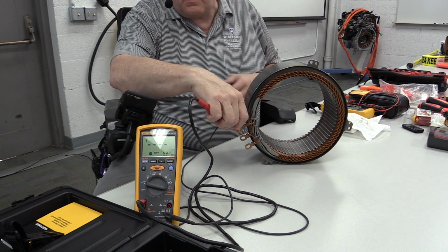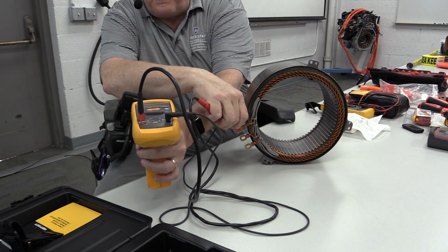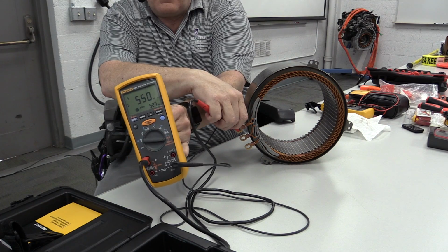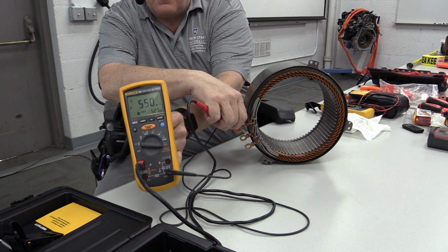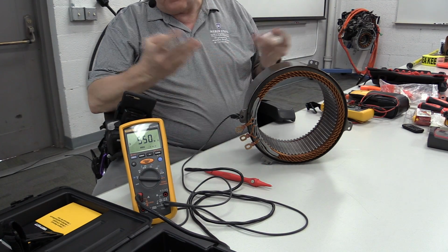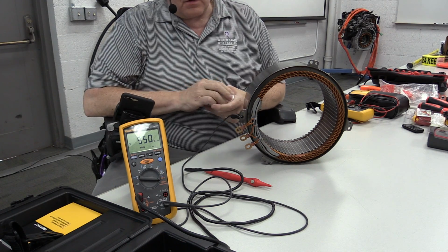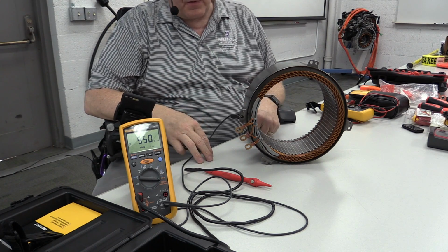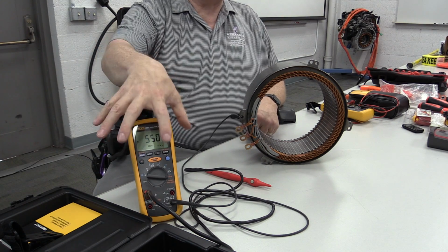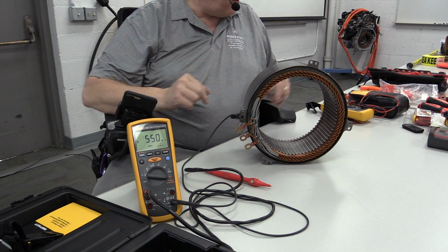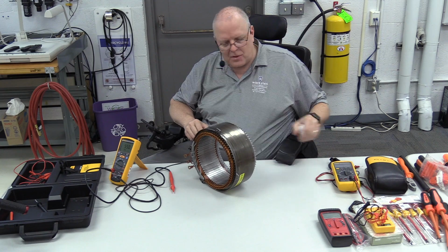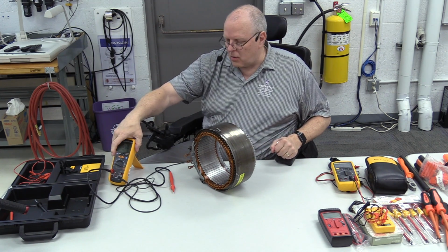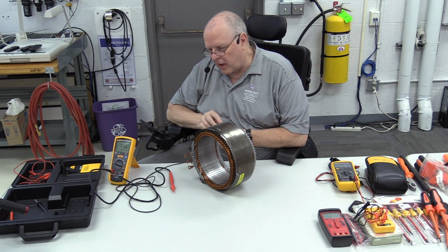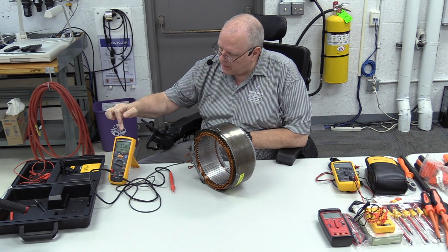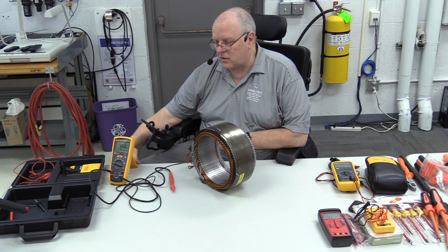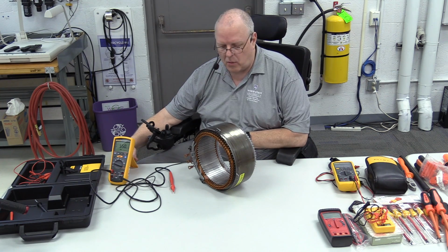And on 500 volts, I'll touch right here. I'll press the button on the lead, and now we've got 550 million ohms. 550 megohms at 500 volts. So the amount of voltage applied affects the resistance. So still there's a minimum specification there. Now this is more realistic, and that's why they're using this meter to check these, because these don't run on the 2.7 volts that the other meter uses to check resistance. So that's why we have the insulation tester, or megohmmeter as other meter manufacturers call it. So Chrysler, General Motors, even Toyota call for this Fluke 1587 insulation tester. I'm sure others do also, because it seems to be a wonderful meter.